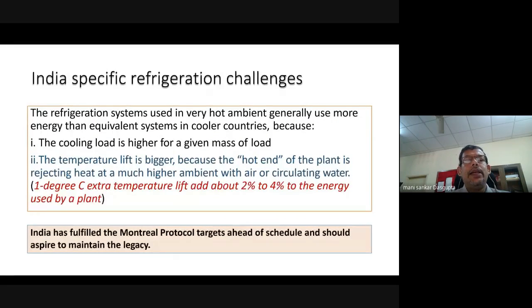The temperature lift is bigger at the heat rejection end, because the hot end of the plant needs to reject heat at much higher ambient temperature, which may be at 45 degrees—so you need to push up the temperature to 50 degrees to have a delta T to reject the heat. One degree centigrade of temperature lift adds about 2 to 4% to the energy demand of the plant, so the efficiency of refrigeration plants used in dairy or any other industry in India cannot be compared to a similar plant used elsewhere—plants need to be designed for specific purposes.